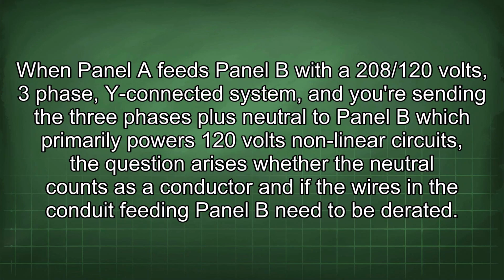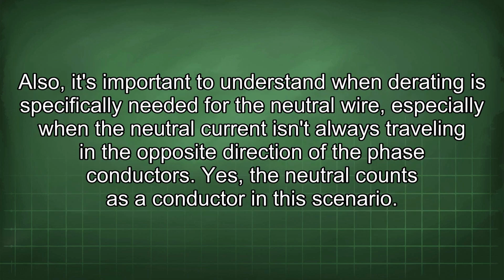When panel A feeds panel B with a 208/120 volts, three-phase, Y-connected system, and you're sending the three phases plus neutral to panel B, which primarily powers 120 volts nonlinear circuits, the question arises whether the neutral counts as a conductor and if the wires in the conduit feeding panel B need to be derated. Also, it's important to understand when derating is specifically needed for the neutral wire, especially when the neutral current isn't always traveling in the opposite direction of the phase conductors.